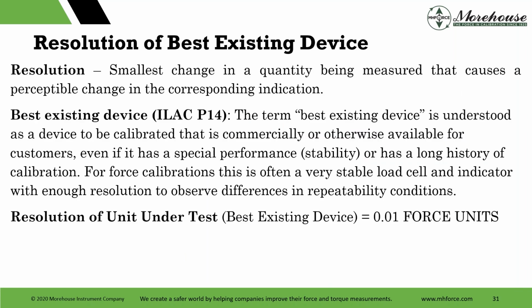The other contributions there, resolution, look, that's what you're reading. The smallest change in the quantity being measured. And then we have ILAC P14 definition. Some people just throw that in there. Best existing device is understood as a device to be calibrated that is commercially or otherwise available for customers, even if it has special performance stability or has a long history of calibration.